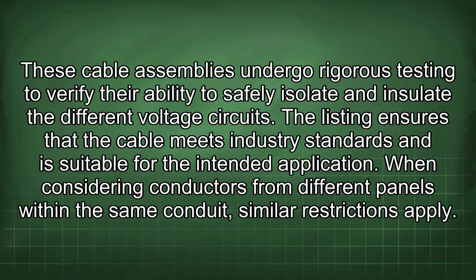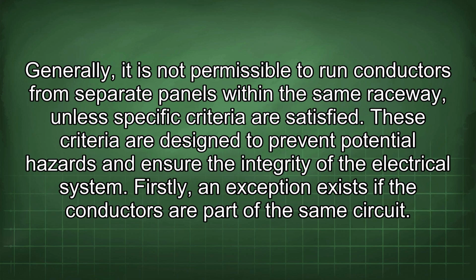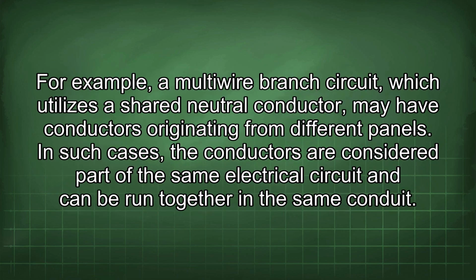When considering conductors from different panels within the same conduit, similar restrictions apply. Generally, it is not permissible to run conductors from separate panels within the same raceway, unless specific criteria are satisfied. These criteria are designed to prevent potential hazards and ensure the integrity of the electrical system. Firstly, an exception exists if the conductors are part of the same circuit. For example, a multi-wire branch circuit, which utilizes a shared neutral conductor, may have conductors originating from different panels. In such cases, the conductors are considered part of the same electrical circuit and can be run together in the same conduit.